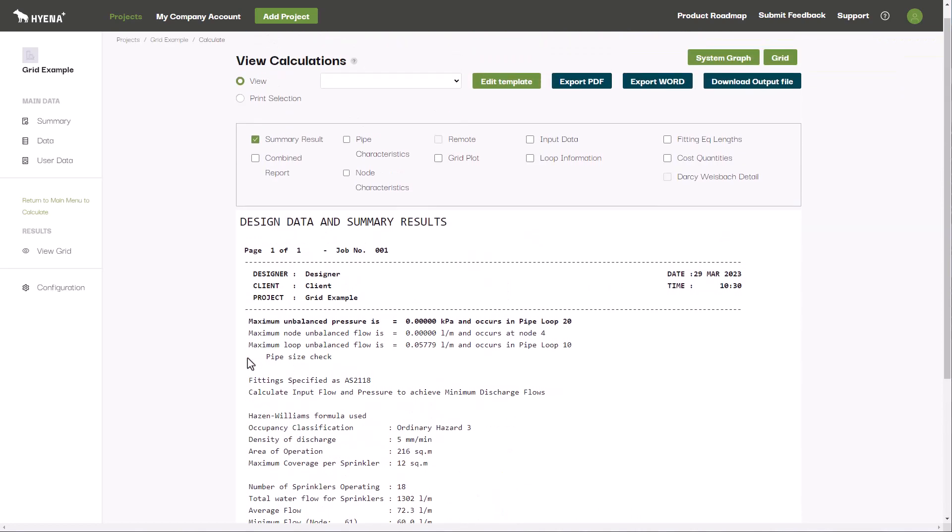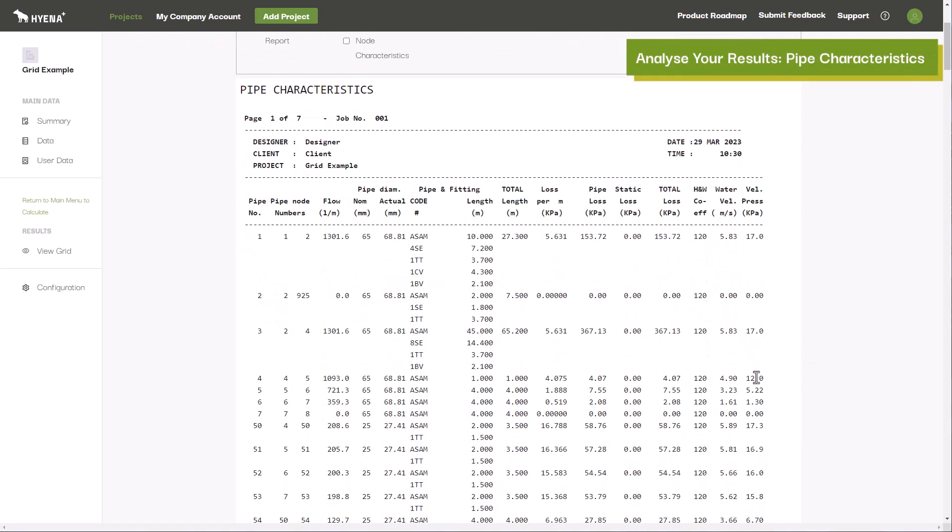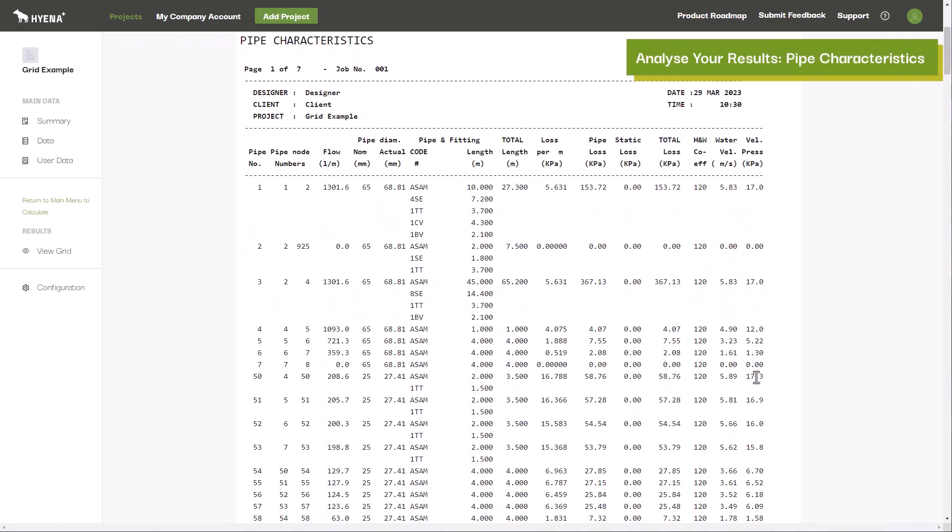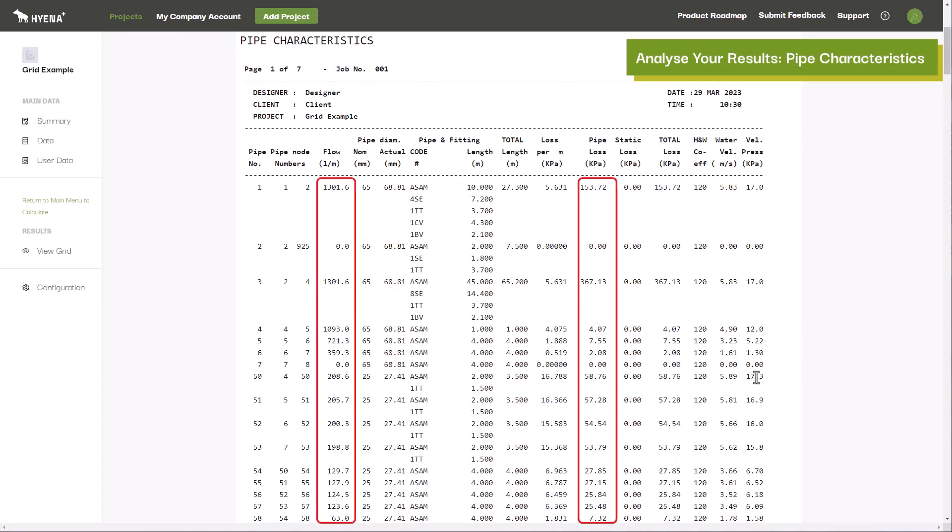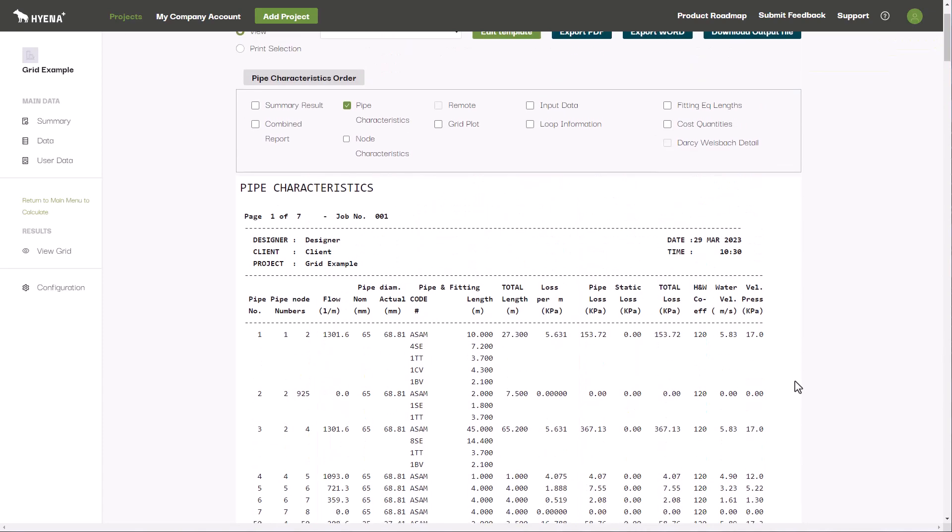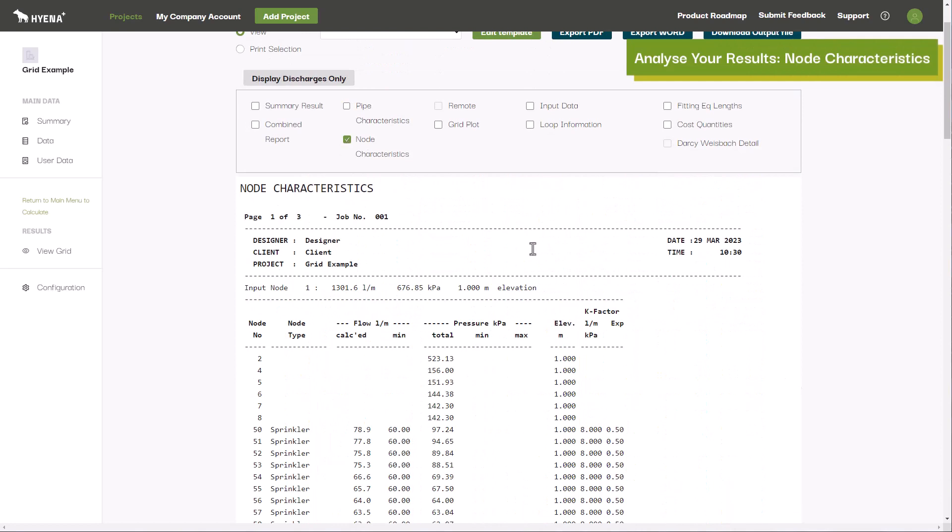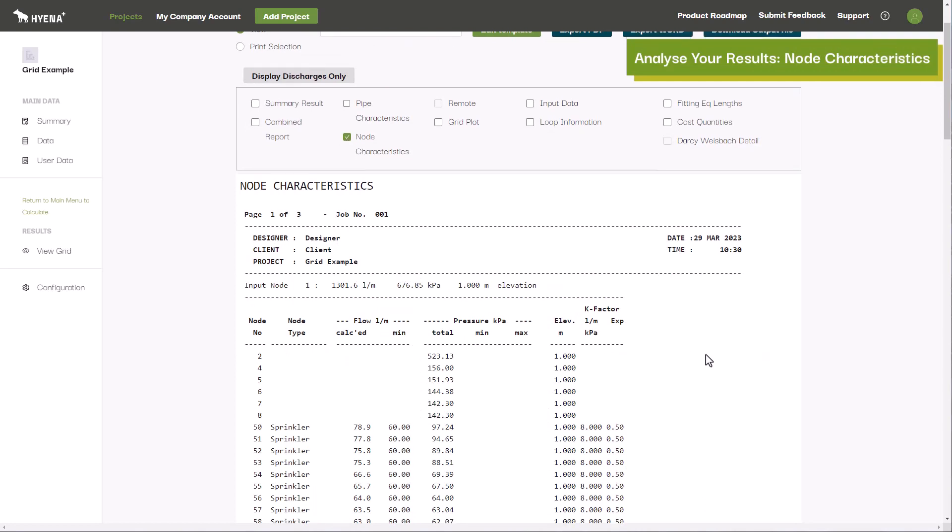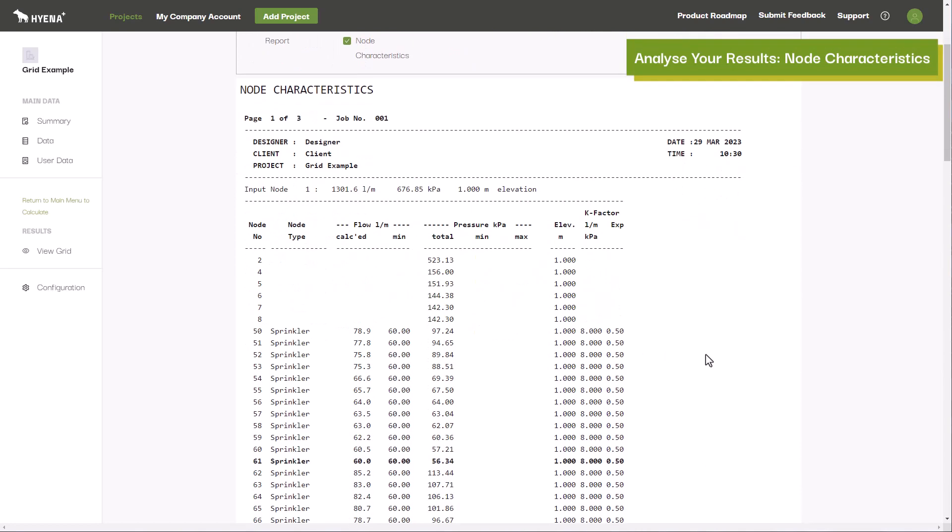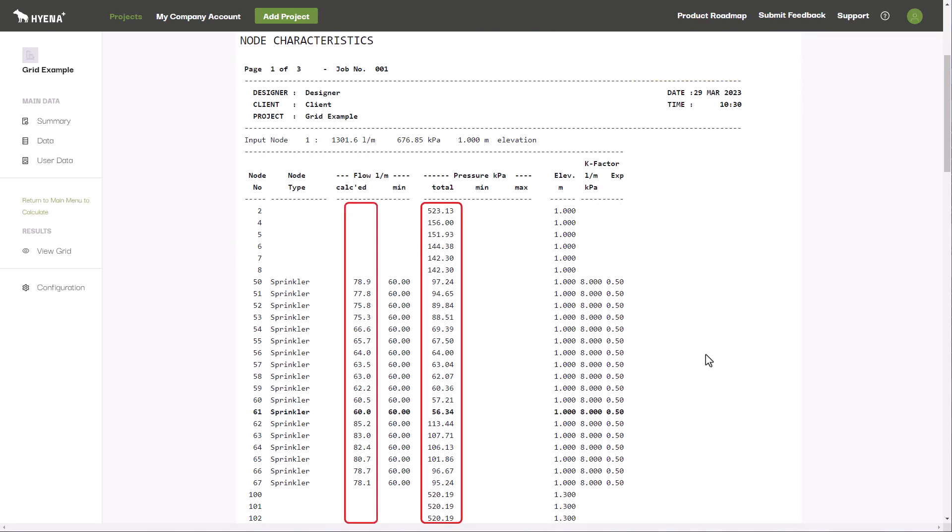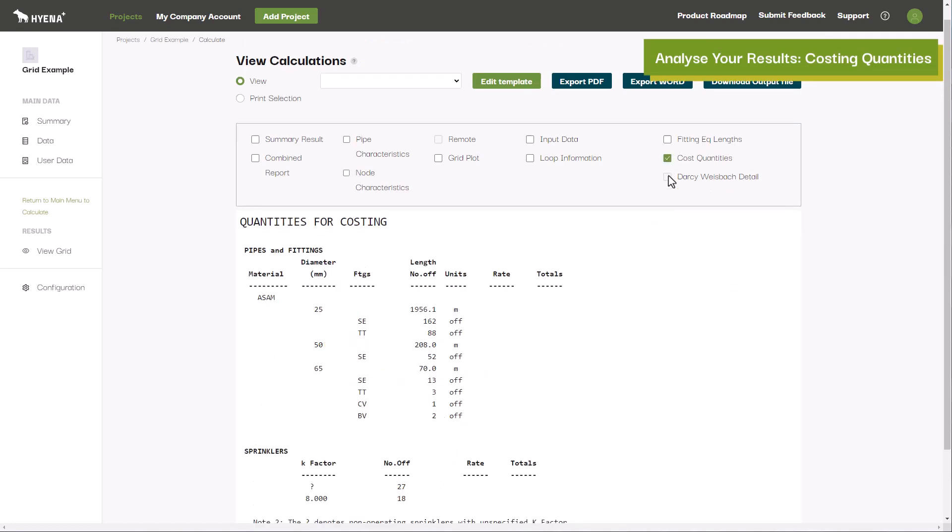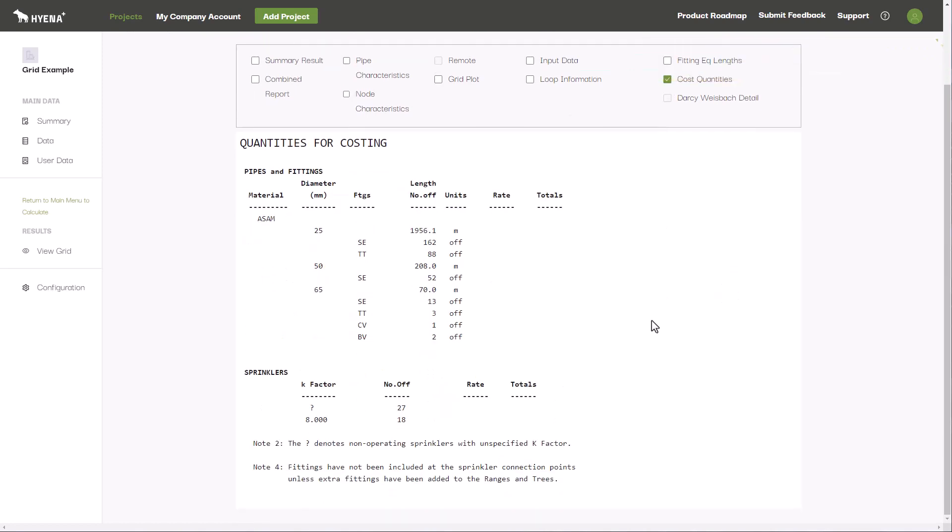You can dive deeper into the results by clicking the pipe characteristics button to view the details and pressure dropped through each segment of pipe in your network. Clicking the node characteristics button, you can view the pressure at each node in your network, as well as the discharge flows through each nominated discharge point. You can even view a summary of pipe and fitting quantities and sizes for costing purposes.